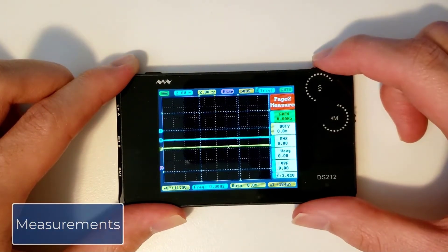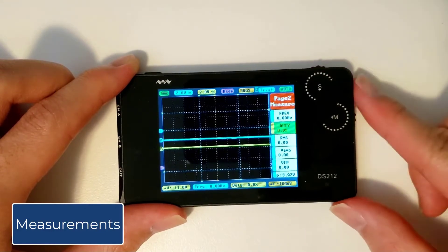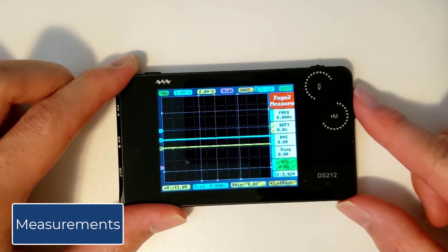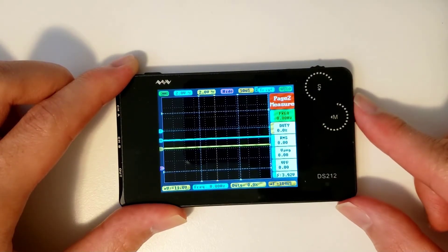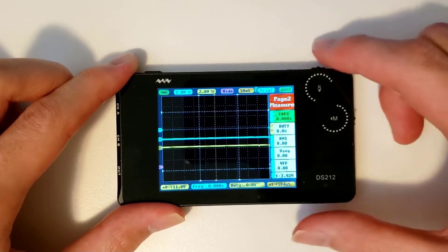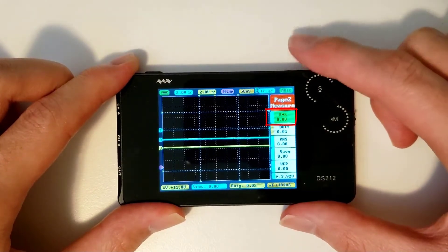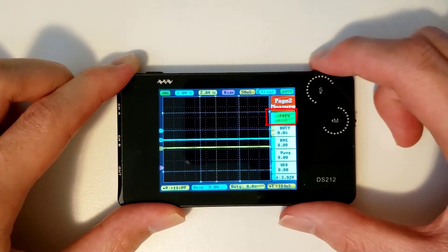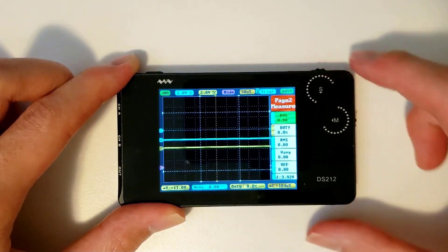If we move on to page 2 by clicking the S wheel, we can see five measurement slots. We can set each slot to measure what we want by hovering over it and scrolling the S wheel, or by clicking the M wheel to enter the submenu for that slot.